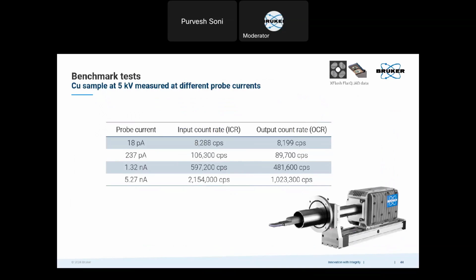So these were some benchmark tests that I did with the flat quad. I used the lowest possible probe current on a copper sample at 5 kV, and I wanted to see how much input and output count rates I got, so mainly input count rate. At 18 picoamperes, I could get around 8,000 counts per second. And at 237 picoamperes, it was over 100,000 counts per second.